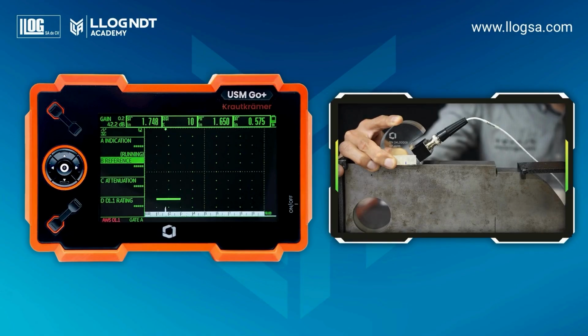Once obtained, and without moving the transducer, adjust the gain so that the echo reaches an amplitude between 40% and 60% of the vertical scale. For this example, we will use 50%.